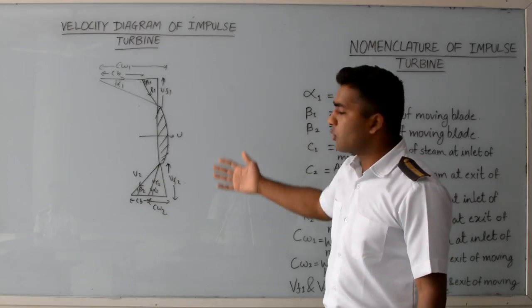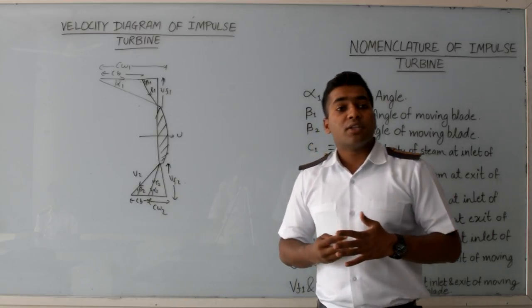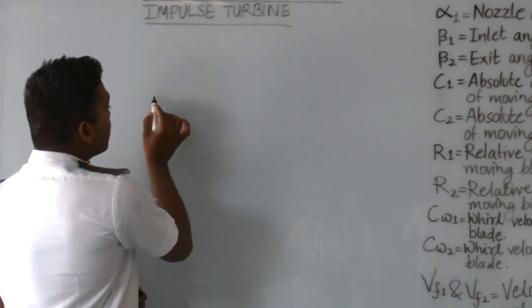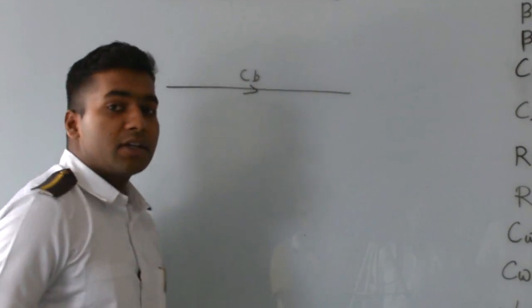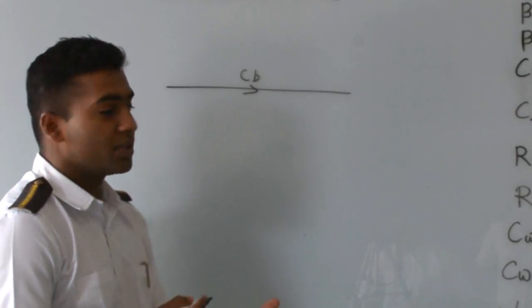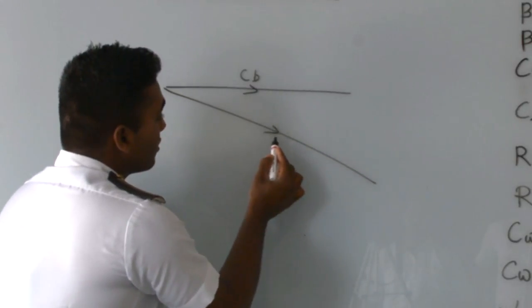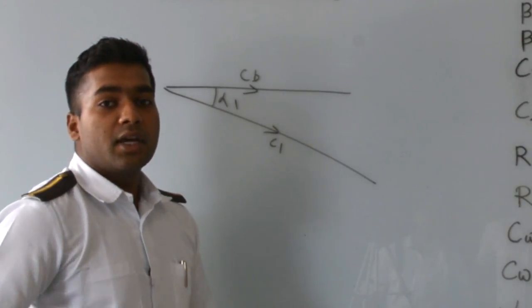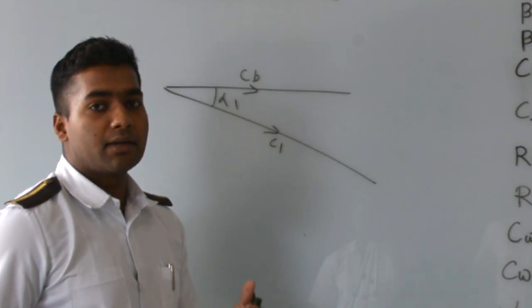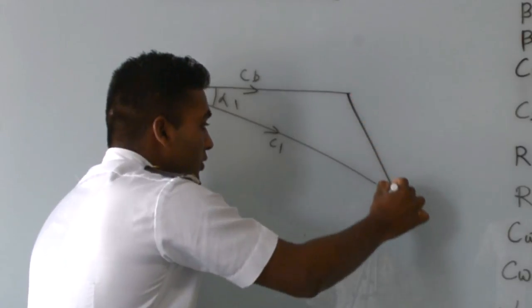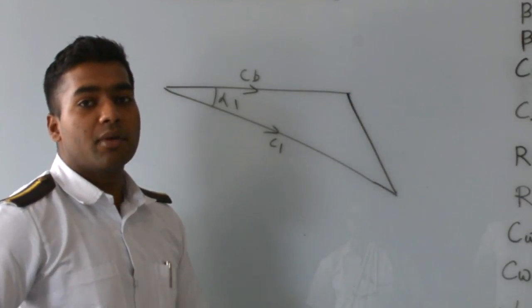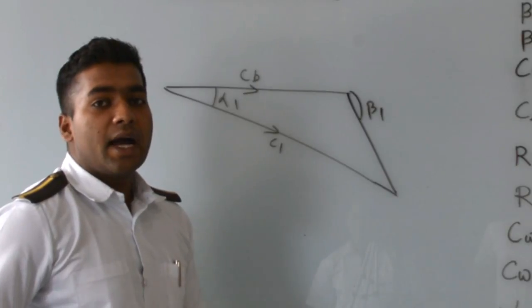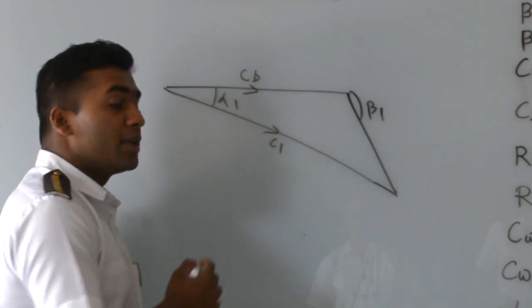Now I will explain the combination of inlet and outlet velocity triangles, which is very important when solving numerical problems on steam turbines. The blade moves with linear speed Cb. Steam enters at an angle alpha1 with absolute velocity c1 from the nozzle. Due to the blade's linear velocity, a relative velocity r1 is created at inlet angle beta1. Steam leaves the moving blade at angle beta2 with relative velocity r2.